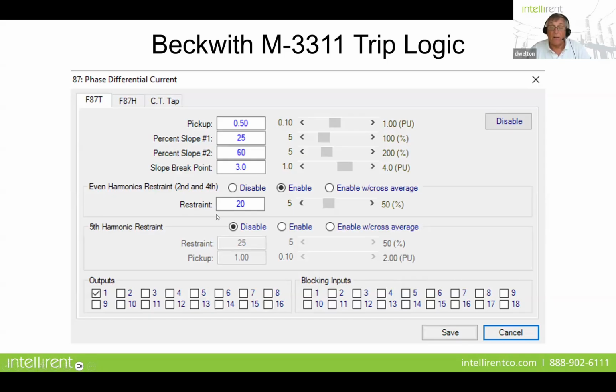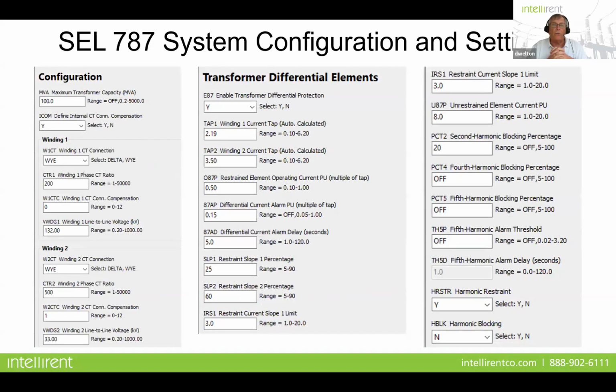Okay, and then a second harmonic restraint and an output that goes to the main trip contact of the relay. So this is all fairly simple and very intuitive. If we look at the Schweitzer, it's a little bit different. Again, we see the MVA rating. We see how you've got a Y connected primary with a CT ratio of 200 to 1.